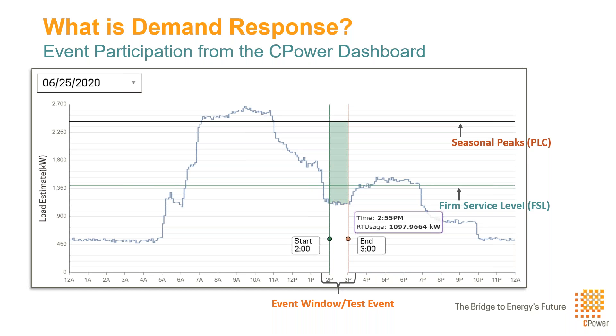This is not an all-or-nothing participation program. You don't need to reach a hundred or a hundred and ten percent to receive the full incentive. Anytime your site is below your seasonal peak — whether summer or winter — during a test event or emergency event, you're showing compliance. Even if you're at 50, 60, or 70% of your required curtailment amount, you're still going to receive an incentive back. Any curtailment put into the market is better than no curtailment at all. The first year is great for working out the kinks and seeing where you can really dial in the facility. As your site becomes more sophisticated, you can dial in the reduction amount each year, and it just becomes a residual annual payment of capacity savings. We have customers that have been participating for 20-plus years throughout the program's inception.